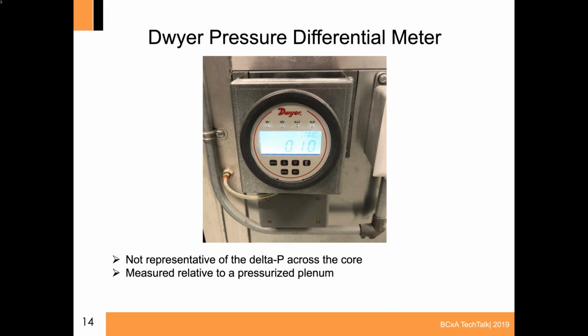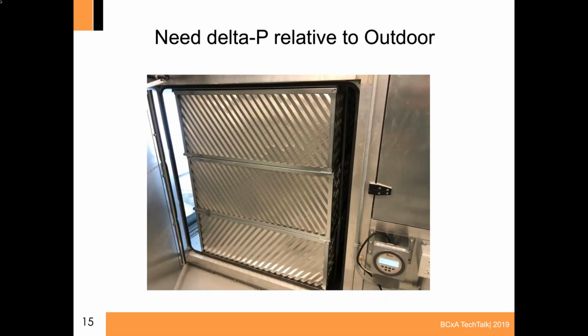So when this is measuring 0.1, this is actually in the exhaust state. When it's in the supply state, it reads a negative number just because of the way the pneumatic tubes are connected. When it goes into its supply, we would actually get an underflow warning and couldn't figure out why that was happening. So we want to be measuring the pressure across the core from left to right. You can see where the daylight is. That's where we want it measured because that's relative to outdoor air.